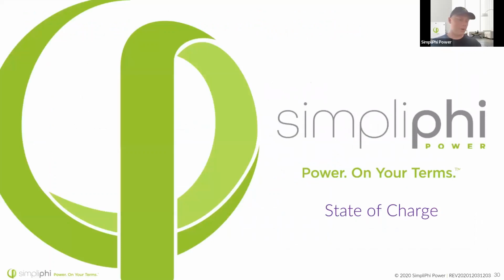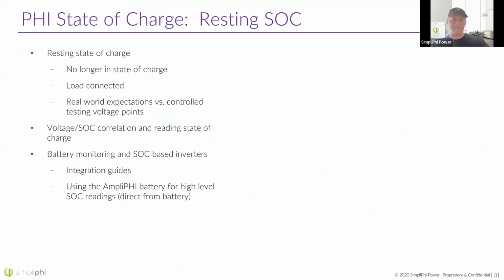Now, let's talk about state of charge. I know we talked a little bit, but it's a touchy subject here. Again, going back to our earlier charts, the voltage is going to greatly vary depending on whether you're charging the device or if you're discharging from the device. So if you've got a single battery at 50% state of charge, you start charging it at C/2, its voltage is going to rise to, let's say, 54.5 or 55 volts even. Now, that same battery at 50% state of charge, you begin to discharge it at C/2, its voltage is going to drop maybe to 51.5 or 52 volts.